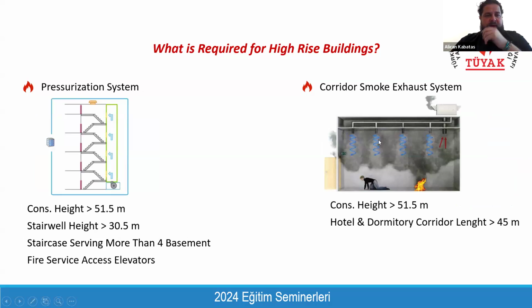And also for the high-rise building, we have a requirement for pressurization system. If the construction height exceeds 51.5 meter, or the height of stairwell from the lower level to the ceiling of the stairwell exceeds 30.5 meter, or the stair serving more than 4 basement floors, it should have a pressurization system. Likewise, if you have a fire service access elevator, it means the construction height exceeds 51.5 meter. This fire service access elevator well should also be pressurized. We will talk about the effects and the consequences of having pressurization system. We need to find a place to locate the fans, and also we need to find a place to locate the shafts, which should be neighboring the stairwell and the elevator well.